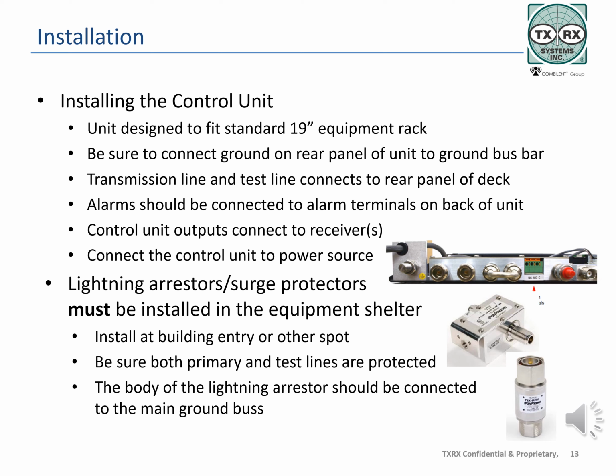When mounting the TXRX Systems control unit in the equipment shelter, again, be certain to follow R56 standards in grounding. The units are designed to be installed in standard 19-inch equipment racks, following the more detailed instruction in the operation manual. Be careful when connecting the rear panel ground lug to the ground bus bar in the rack, being sure that all connections are snugged tightly.